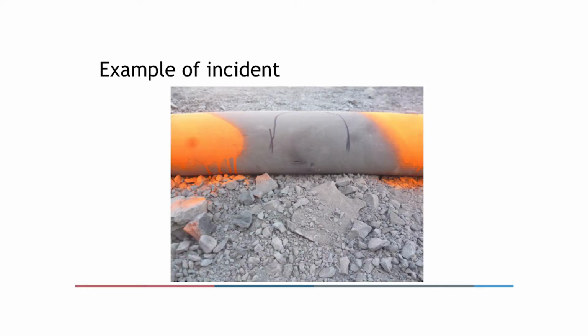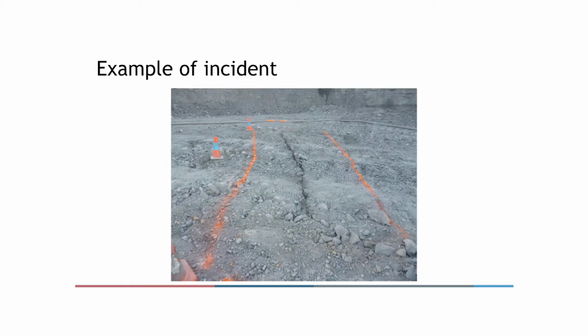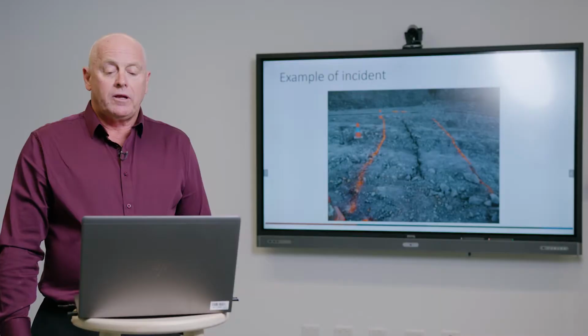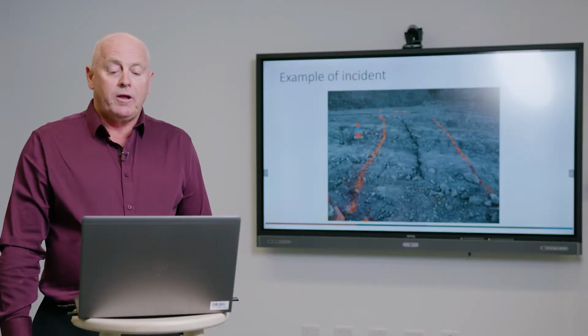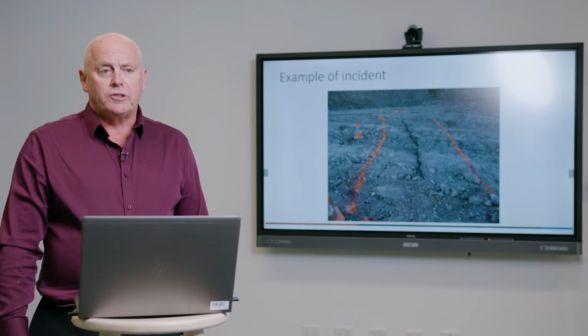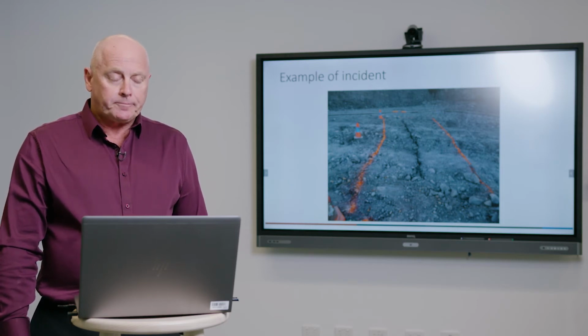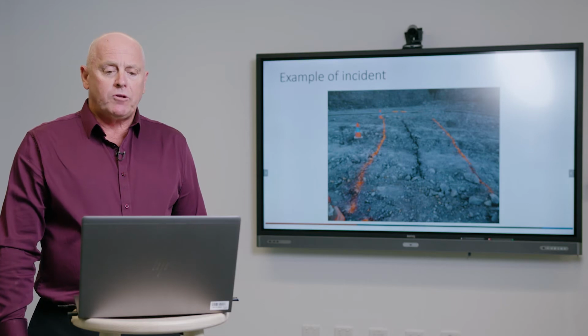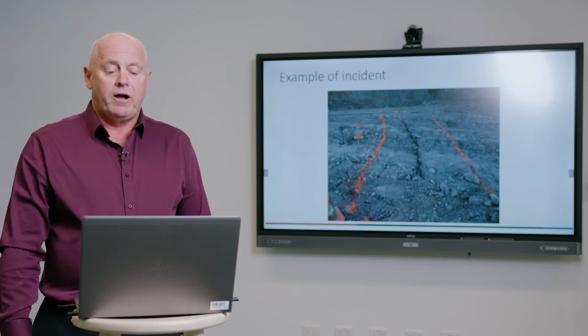Here's a photo of an incident involving an open cut trailing cable supplying a drag line. As you can see, there appears to be minimal damage to the external parts of the cable. The black line you see is from the energy that was still being released over time after the initial fault. The cable was being moved at the time and was pierced by a sharp object. Typically, electrical protection systems should prevent this from happening. However, sometimes these don't and can fail. I can give you some examples of this.